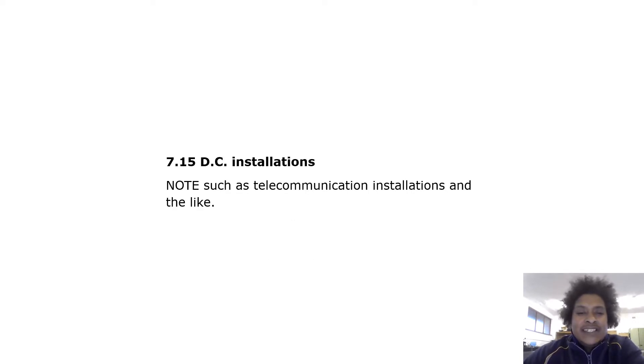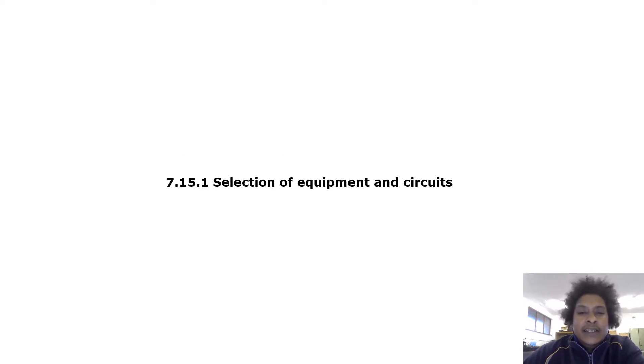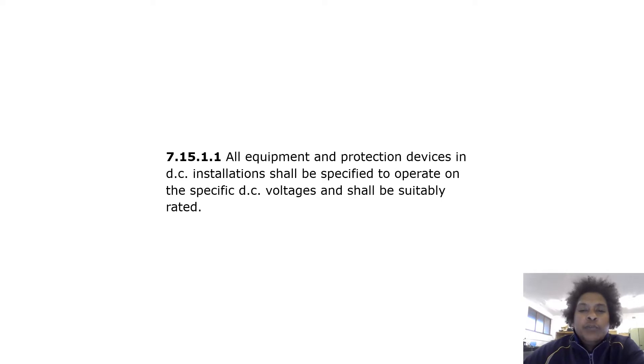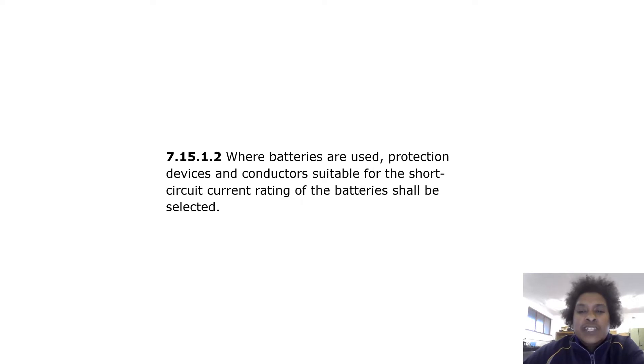DC installations — such as telecommunication installations — require careful selection of equipment and circuits. All equipment and protective devices in DC installations shall be specified to operate on the specific DC voltages and shall be suitably rated. Where batteries are used, protection devices and conductors suitable for the short-circuit current rating of the batteries shall be selected.